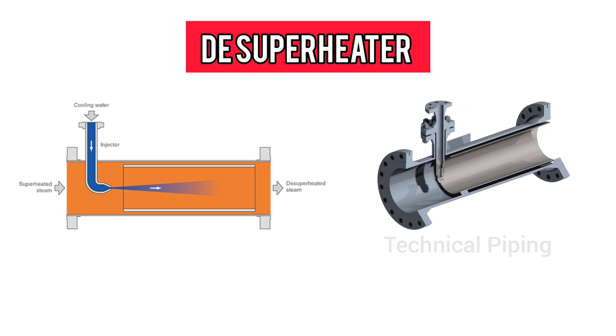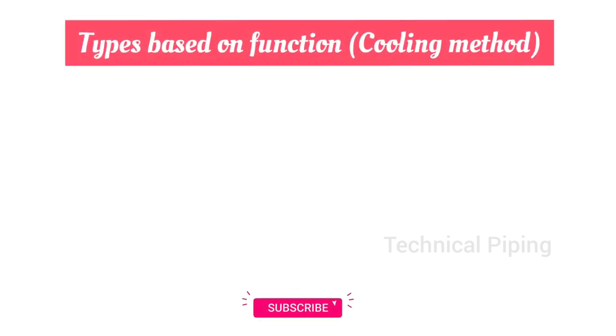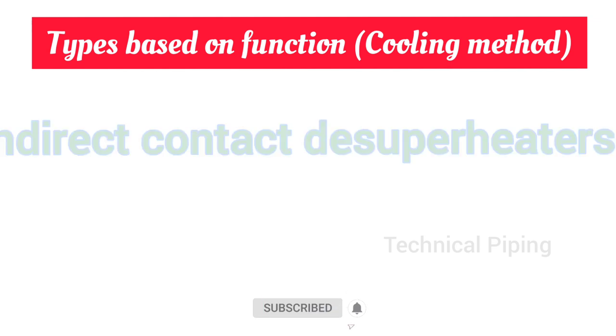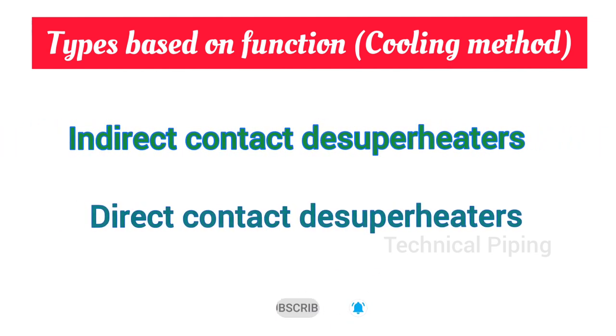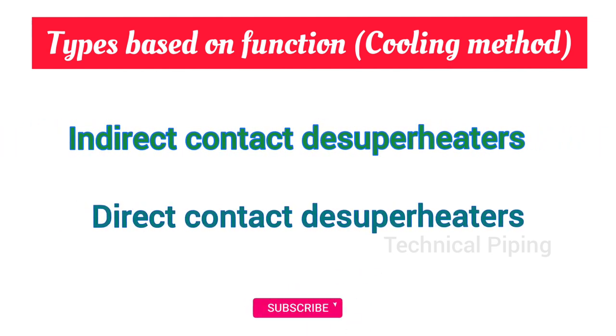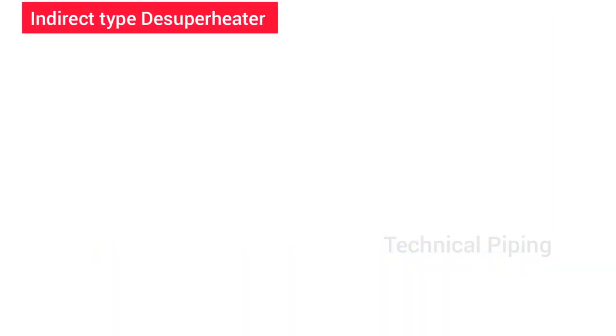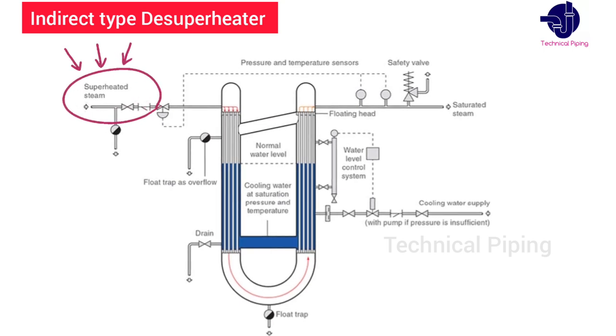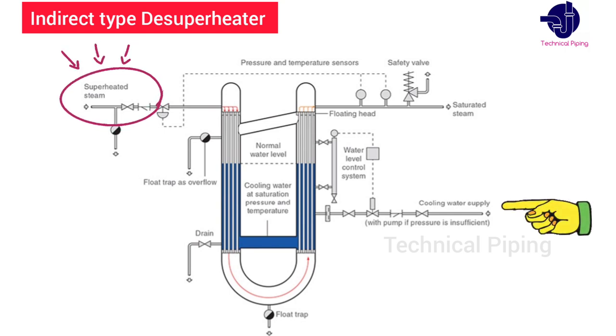The equipment that does this work is called a desuperheater. A desuperheater uses one of two general methods: number one, indirect contact type; number two, direct contact type. In the indirect contact type, a shell-and-tube heat exchanger is used — the superheated steam is passed through the tubes, and the shell contains the cooling medium such as water.